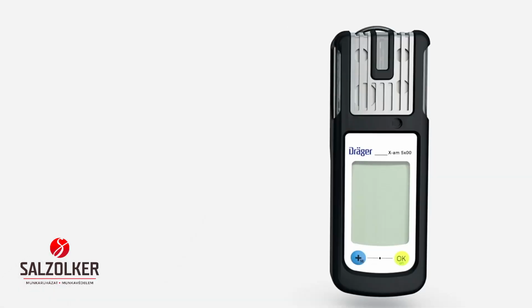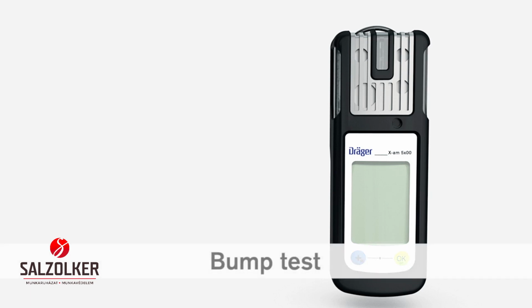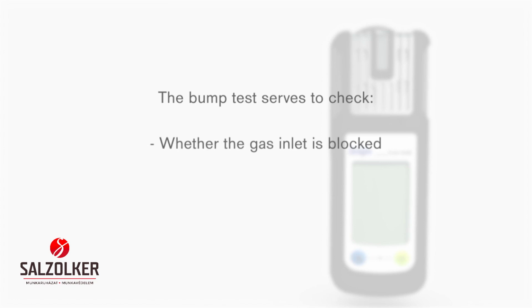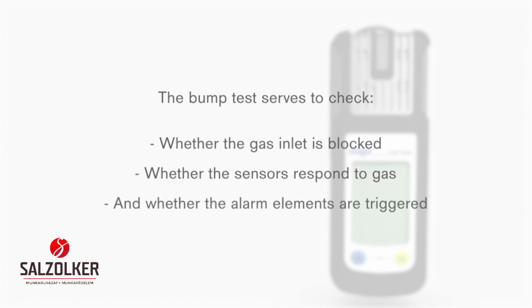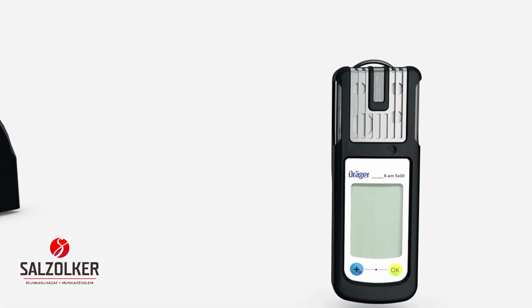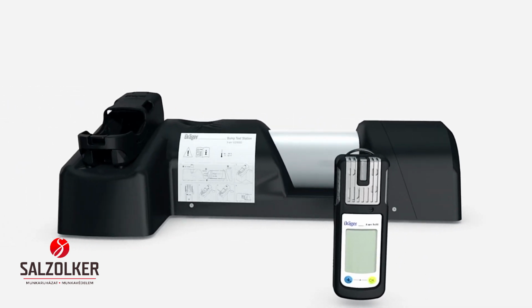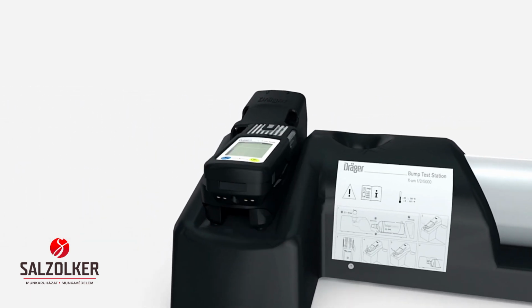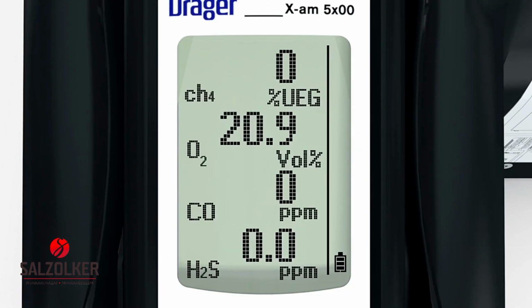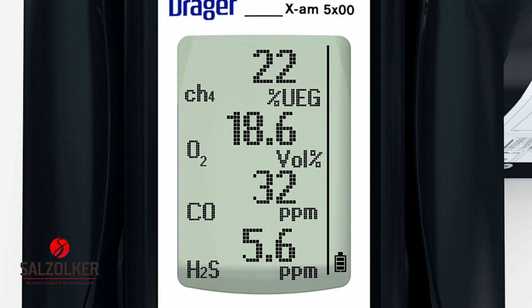www.dräger.com. Depending on the regulations or guidelines, you will first need to perform a function test of your Dräger X-am 5000 or Dräger X-am 5600. The bump test serves to check whether the gas inlet is blocked, whether the sensors respond to gas, and whether the alarm elements are triggered. To do so, insert the device after turning it on. The bump test station automatically identifies the device. The sensors are now automatically purged and the alarms are displayed.